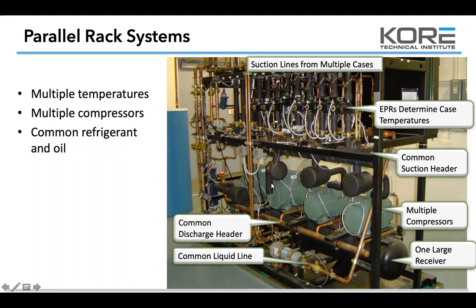Stage one compressor may have an unloader or it may be a variable speed compressor. These are Bitzer Octagon compressors. I like Bitzer compressors because they use a bigger piston and a shorter stroke, so they're a little more robust for taking some liquid than some other brands. Copeland Discus is also very robust when taking a little liquid. Rack systems use a common refrigerant oil, usually visible through the oil separator — that blue cylinder on the end.